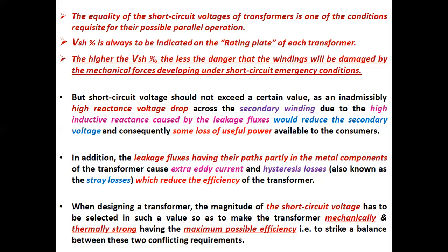When designing a transformer, the magnitude of the short circuit voltage has to be selected at such a value as to make the transformer mechanically and thermally strong, having the maximum possible efficiency. That is, to strike the balance between these two conflicting requirements.